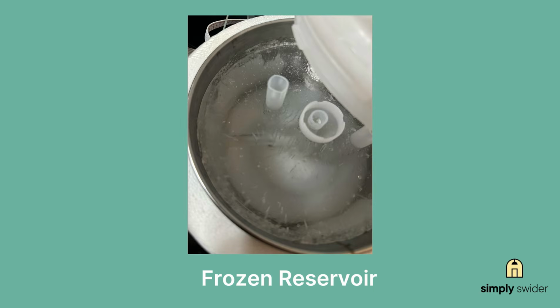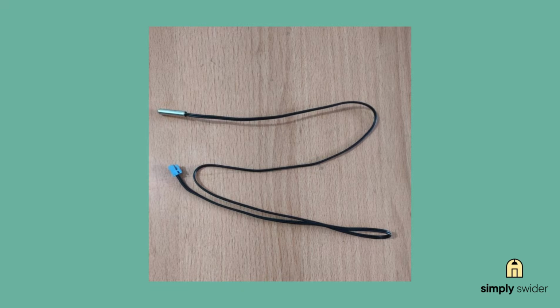Here's one that throws people off. About 20% of the time, that cooling system works too well and freezes the whole reservoir solid. I've seen units where the water turns into a complete ice block, and obviously nothing's going to flow through that. This usually happens because the temperature sensor goes bad, the digital settings are too low, or the unit's too close to the wall and can't breathe properly.